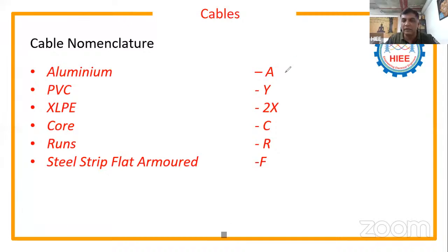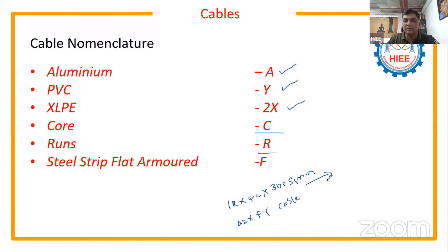Generally, if the conductor is aluminum, your cable is represented with A, PVC insulation is represented with Y, and XLPE will be 2X. You just note this down. This is very, very important. Generally we don't mention core, and the number of runs is like the number of cores. I told you, if it is a single run of 4 core, C stands for core, and this is a 300 square mm A2XFY cable. This is the nomenclature of the cable.